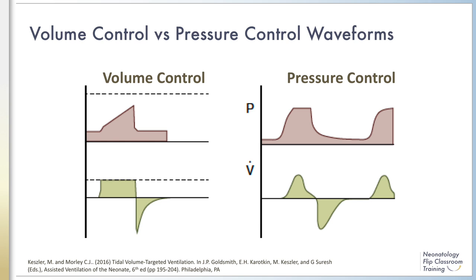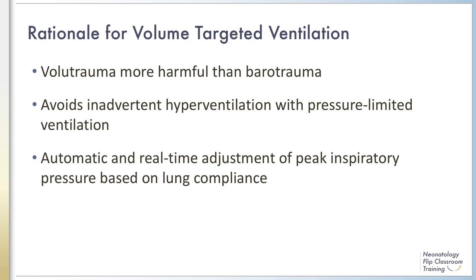In volume control ventilation, the flow is delivered in a square waveform. This indicates flow stays constant until the target volume is reached at the end of inspiration. In pressure targeted ventilation, the flow waveform is sinusoidal and the opening pressure is reached quickly. After the target pressure has been reached, flow decelerates rapidly until inspiration is complete.